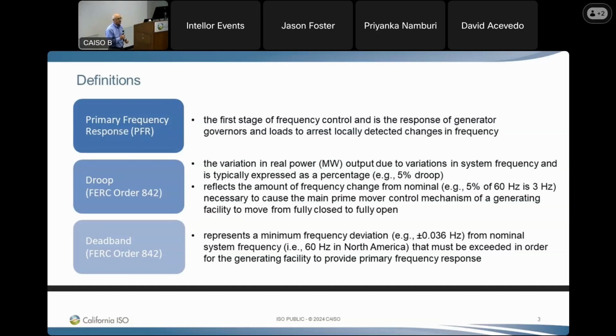And with IBRs, everything is software and hardware driven. The controller will establish what your frequency response is going to be. It is looking at what the frequency on the interconnection is, and as soon as it goes outside of that dead band, it goes ahead and provides the appropriate frequency response.